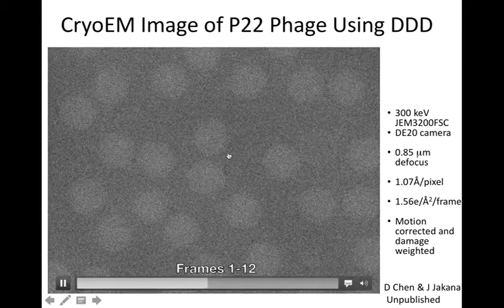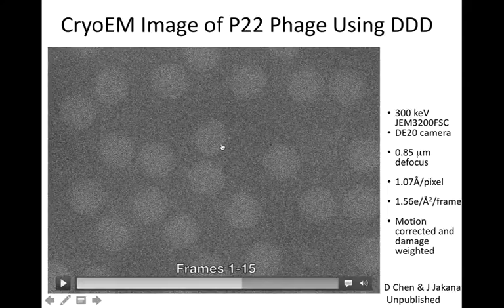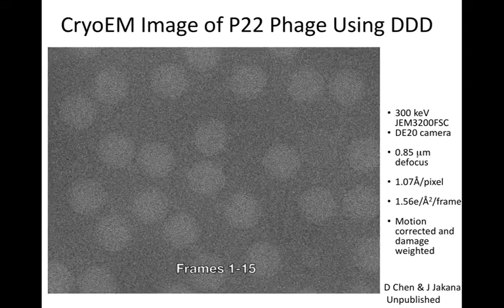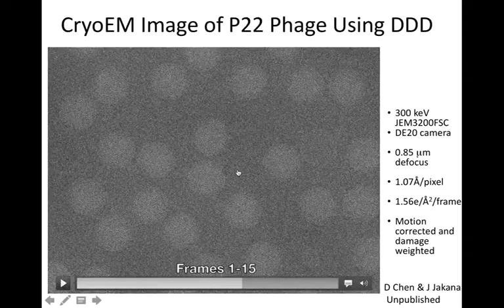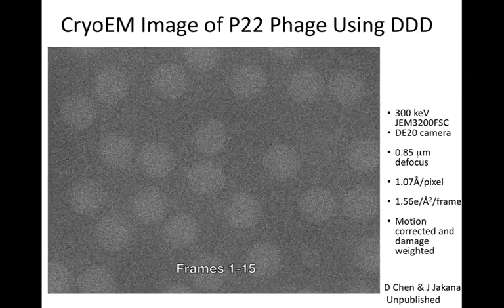Now, why is it important to have this capability to align different frames? Because when the electron hits the specimen, it has a tendency to move around under the electron beam. But with post-data acquisition alignment, frame after frame, we can put all the frames in register in such a way that the image can be much sharper than just purely summing all the frames without registering them.